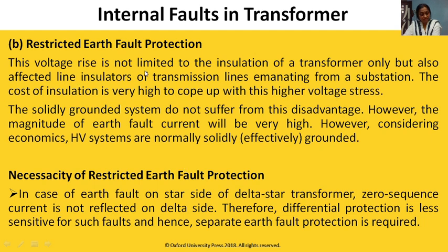This voltage rise is not limited to the insulation of the transformer only, but also affects the line insulators of the transmission line emanating from substation. The cost of insulation is very high to cope up with the higher voltage stresses. So therefore we are using solidly grounded system.